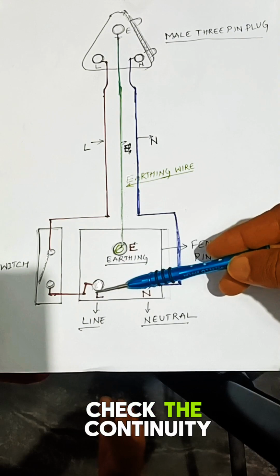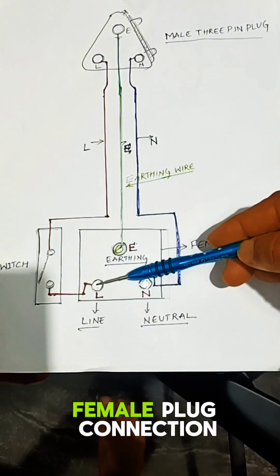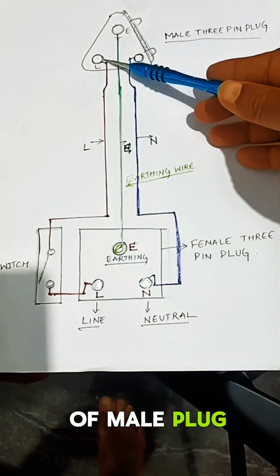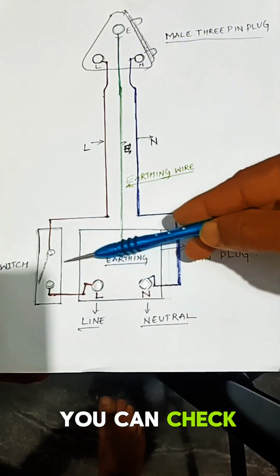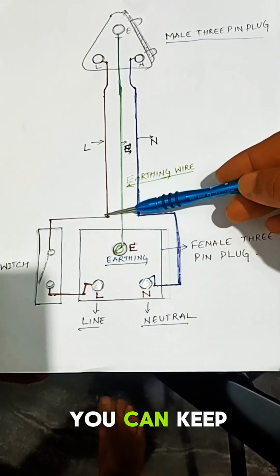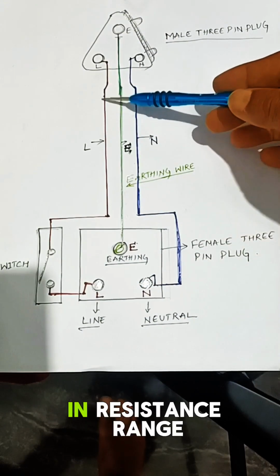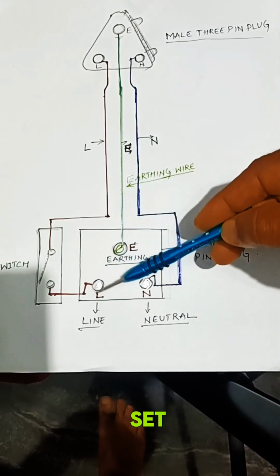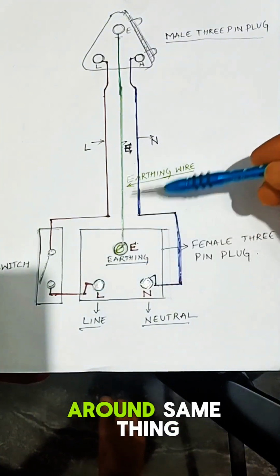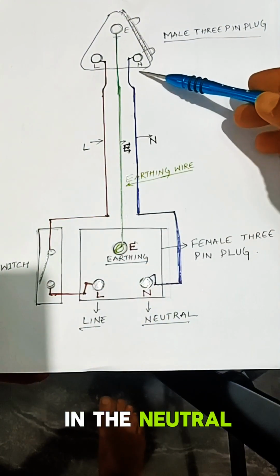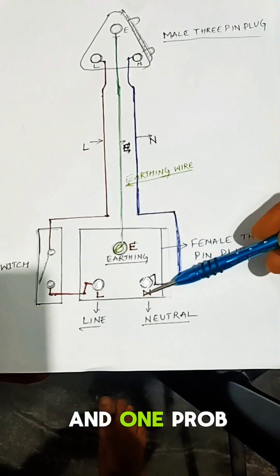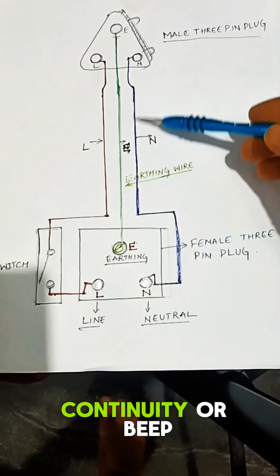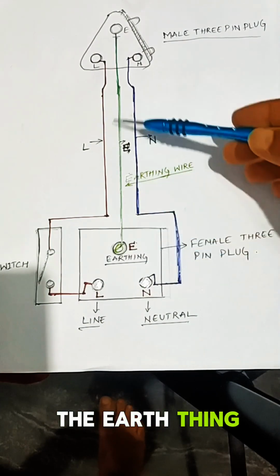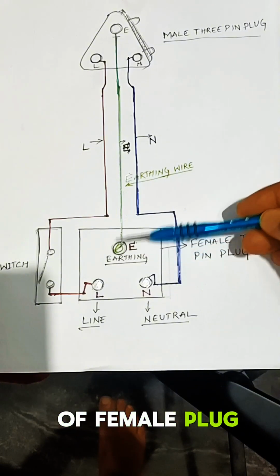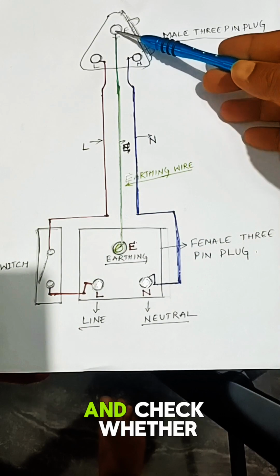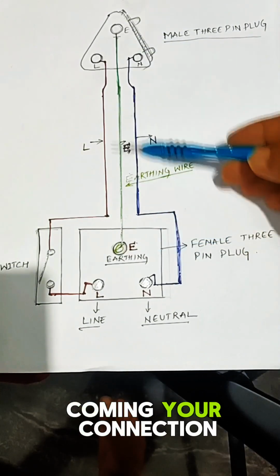Before checking it, check the continuity between the line of the female plug connection and the line of the male plug. For the continuity test, you can keep the multimeter in resistance range and check the continuity. Otherwise, in beep mode, you can check whether the beep is coming or not. Same thing with the neutral wire: keep one probe in the neutral of the male plug and one probe in the neutral of the female plug and check the continuity or beep. Same with the earthing: keep one probe on the earthing of the female plug and one on the male plug and check whether the beep is coming. Once it is coming, your connection is accurate.